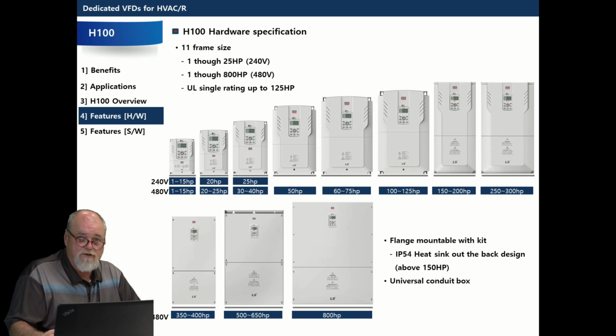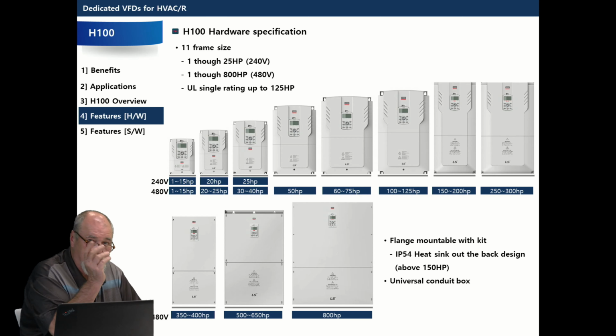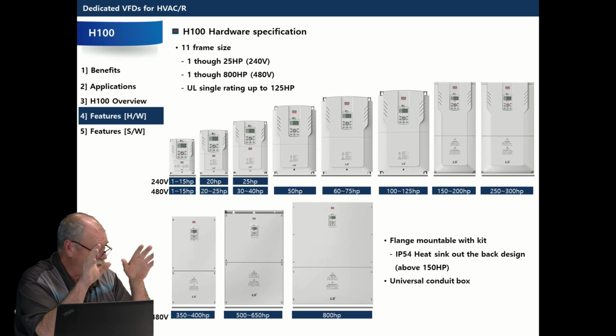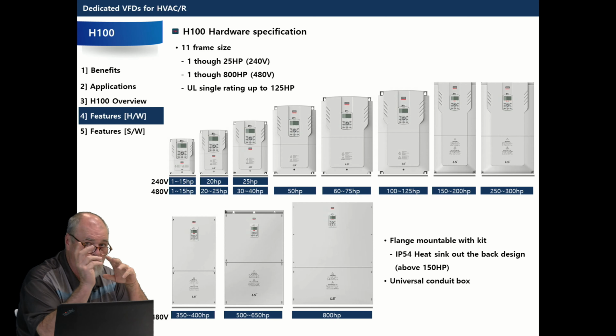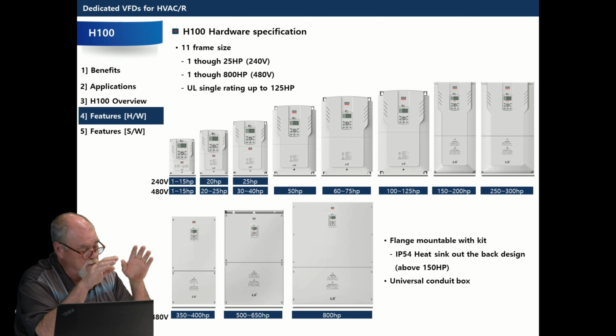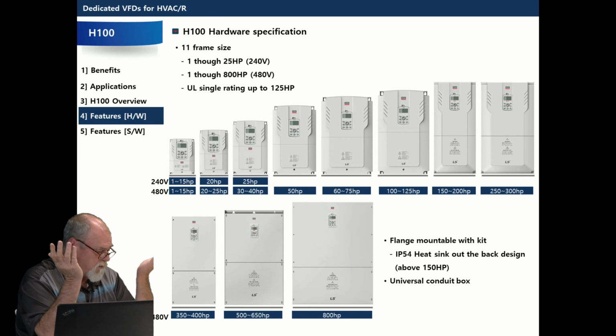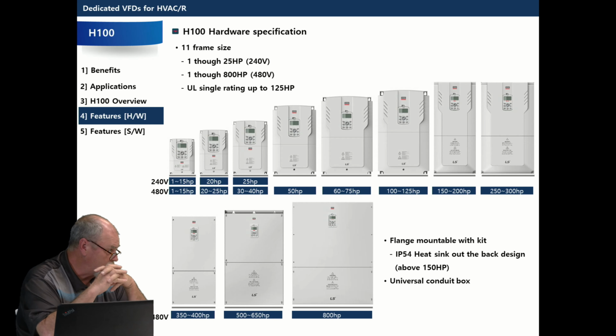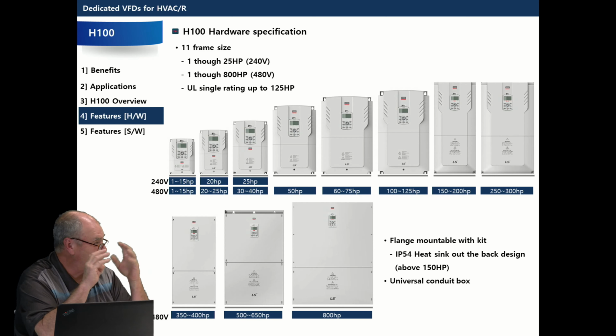Very small footprint. One of the things I like about this, and when you deal with my integrators, is that when you get to 150 horsepower and above, all of our products can have the heat sink out the back of an enclosure, but we still meet a NEMA 12 rating, where most, if not all, can't do that. To give you an example, I just did an 800 horsepower VFD in Southeast Ohio for the fracking industry that may have 10,000 watts of loss. That's like putting a 10,000 watt heater in a box and turning it on. So you have to have a very large box.